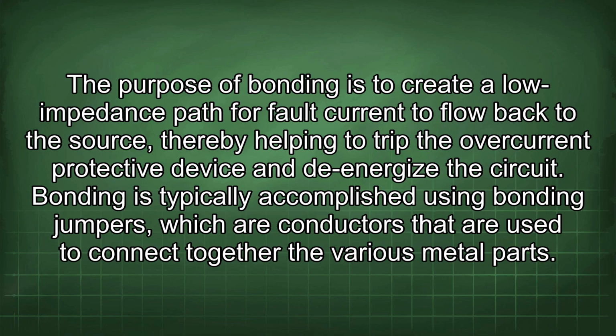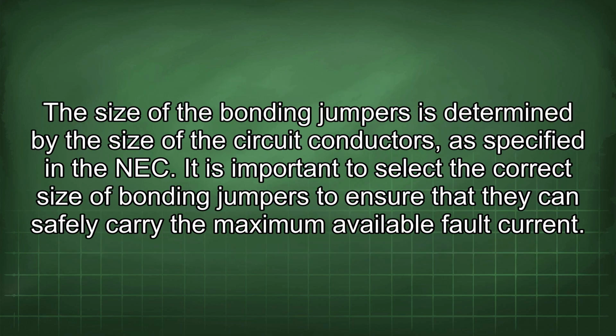Bonding is typically accomplished using bonding jumpers, which are conductors that are used to connect together the various metal parts. The size of the bonding jumpers is determined by the size of the circuit conductors, as specified in the NEC. It is important to select the correct size of bonding jumpers to ensure that they can safely carry the maximum available fault current.